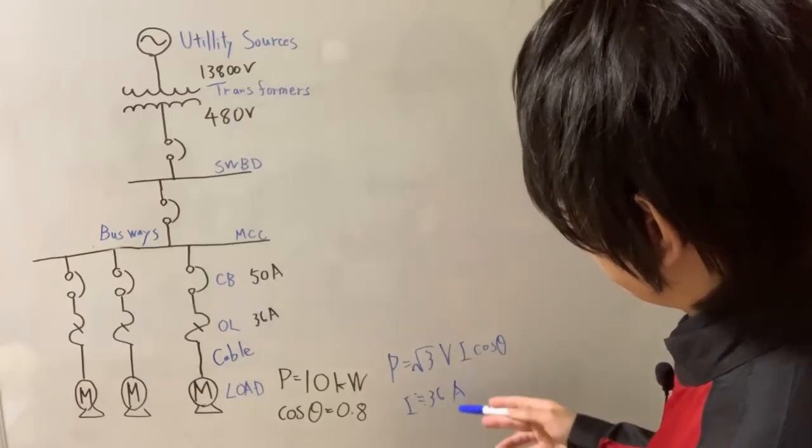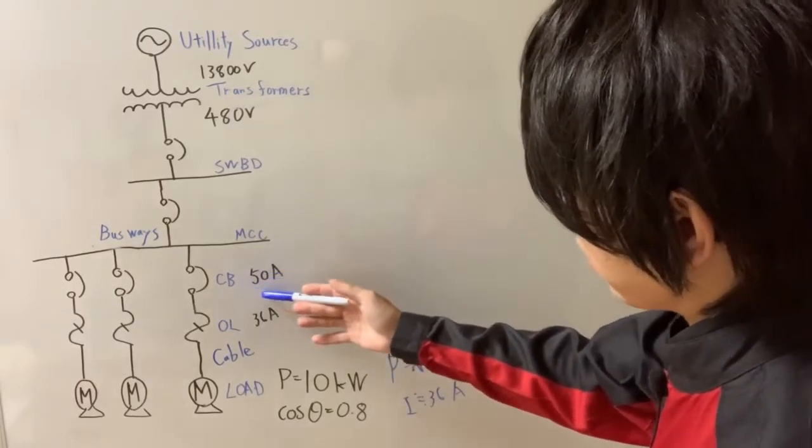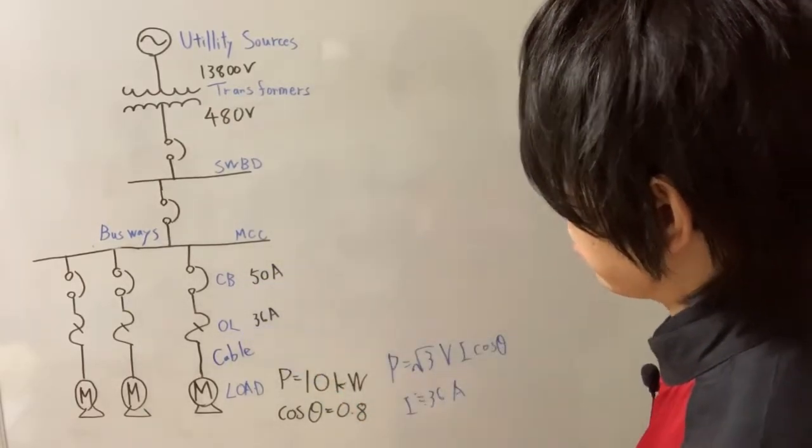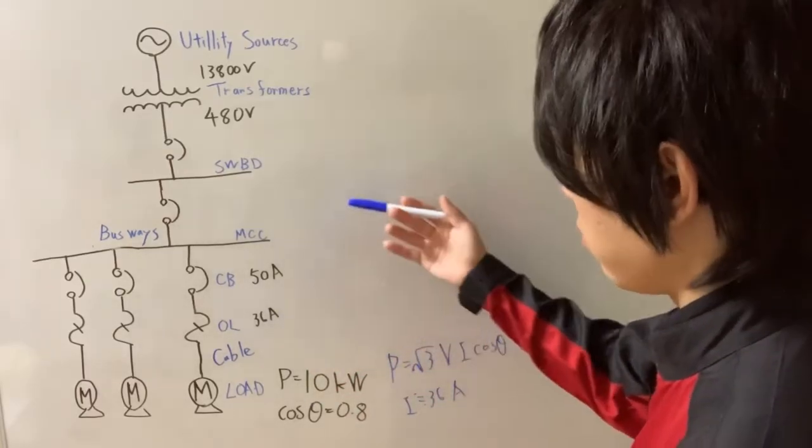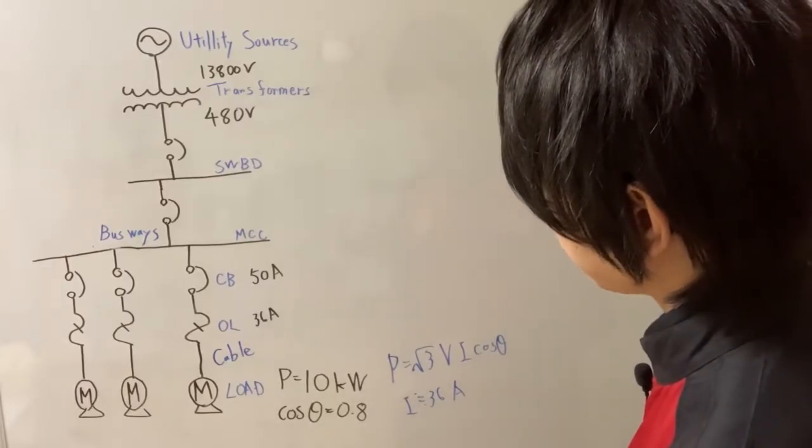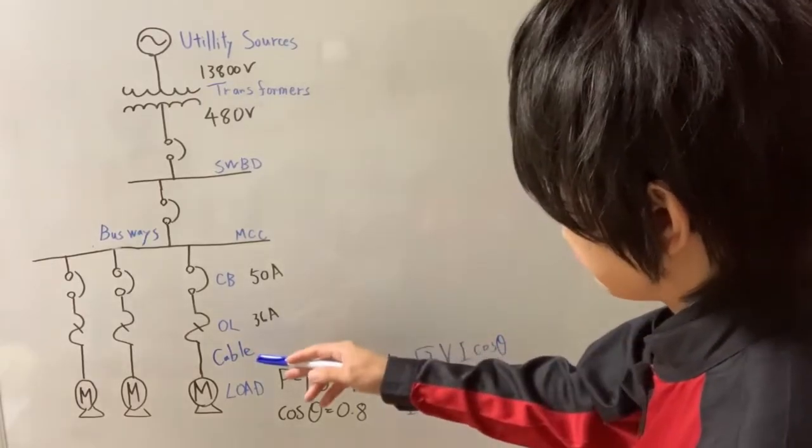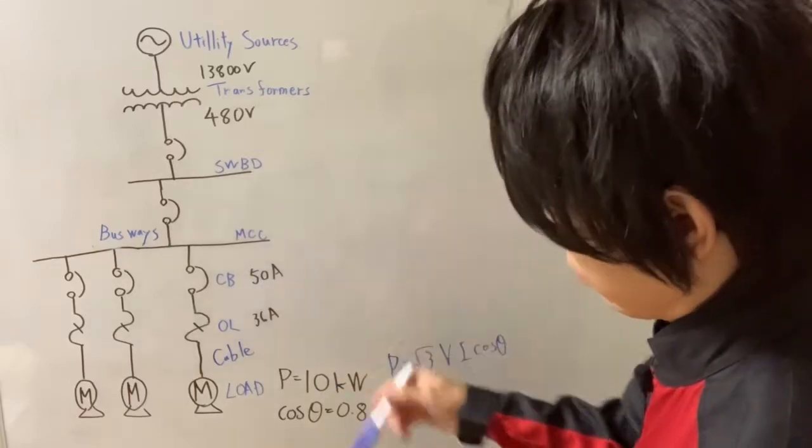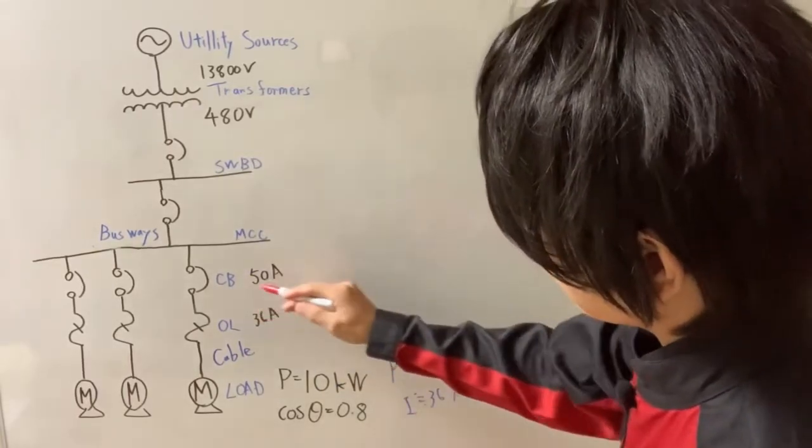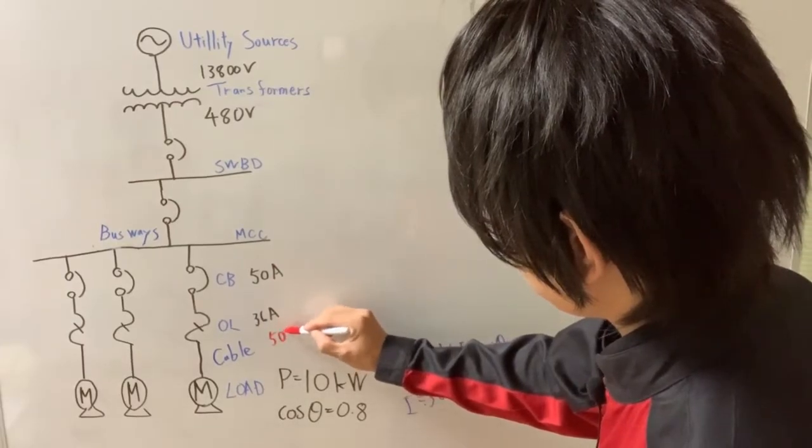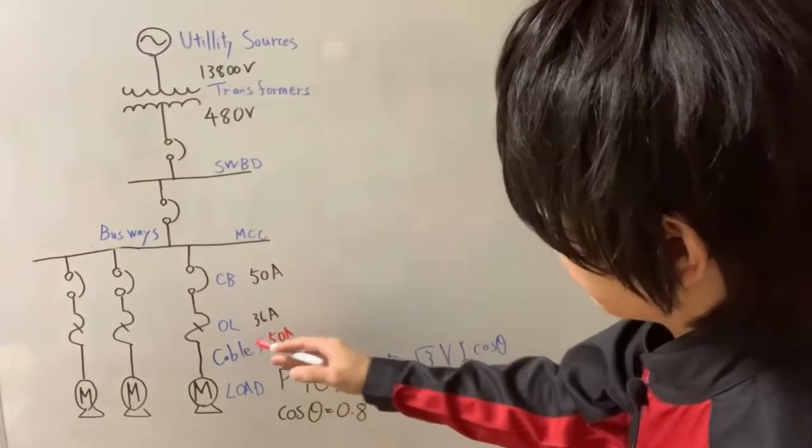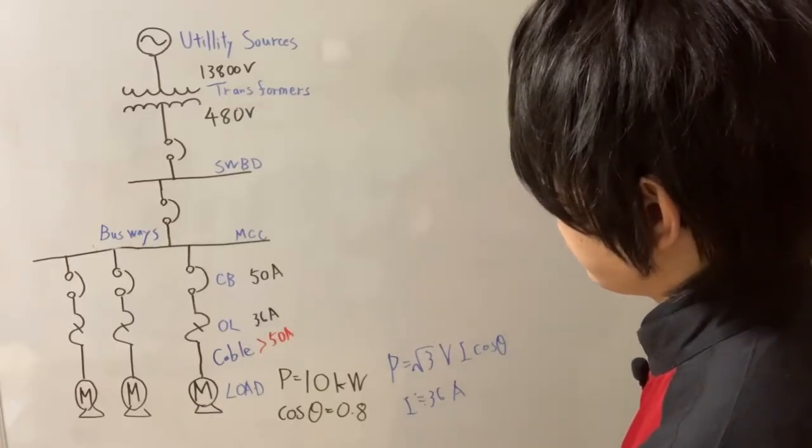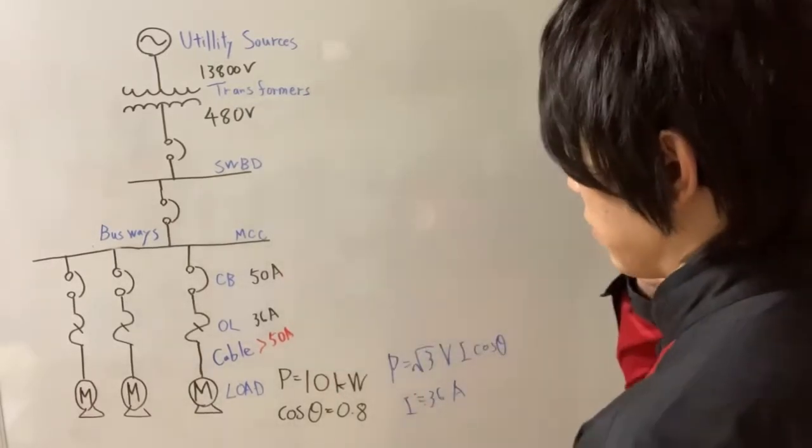That means the protection devices like breaker or relay should be selected as appropriate rating that relates to this maximum load current. So maybe a breaker's trip ampere is 50 ampere, for example, and overload relay setting value is just at 36 ampere or a little bit lower or a little bit higher. And the allowable current of the cable should be greater than 50 ampere because this is protection devices. So cable needs to be protected from some damage.